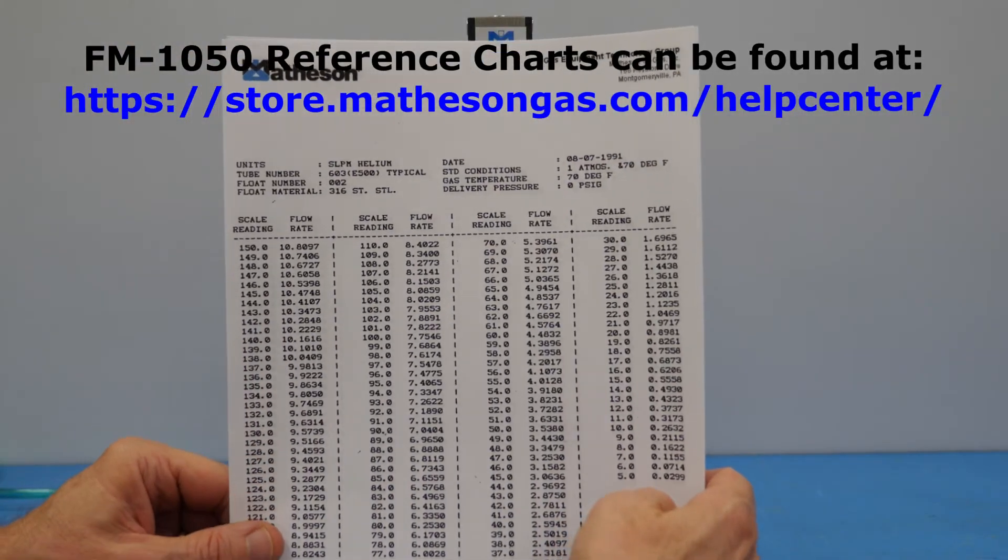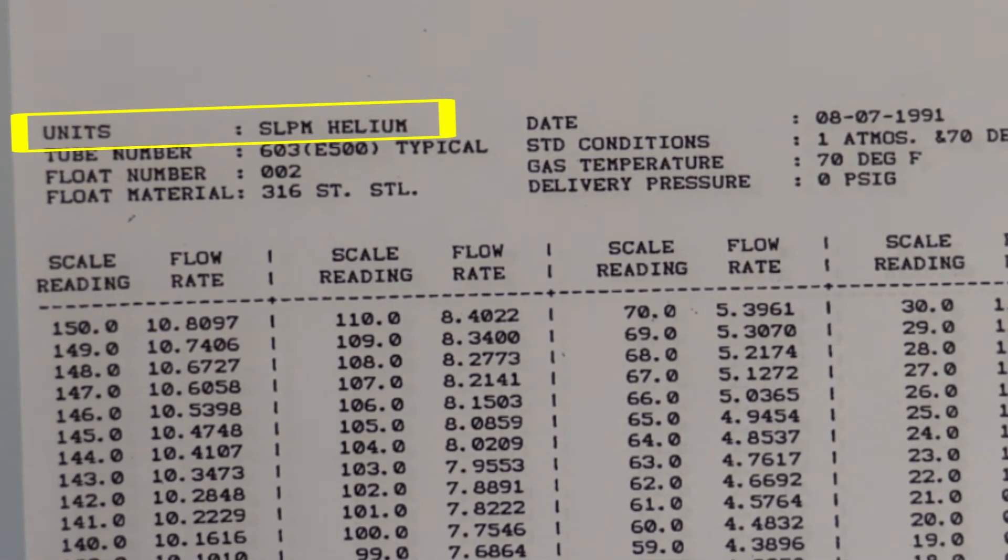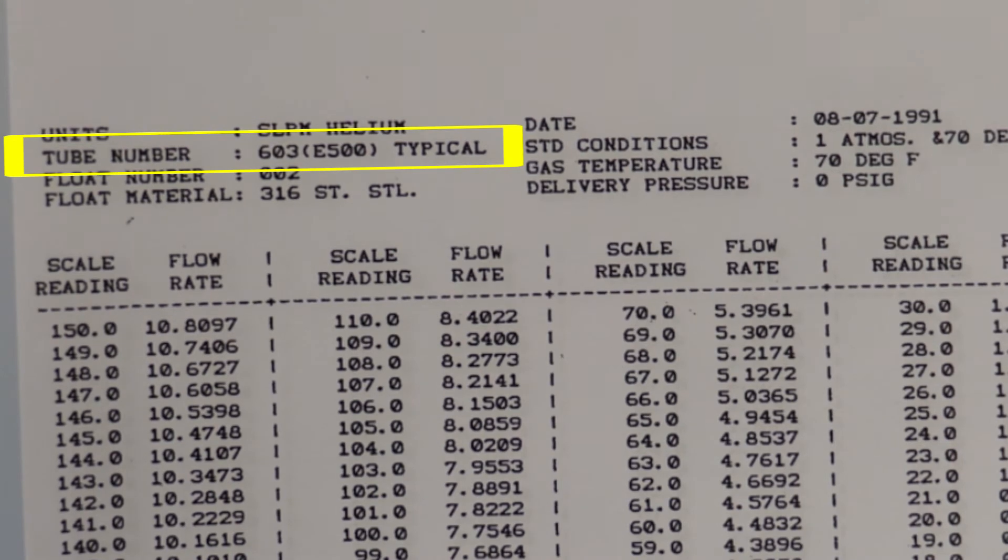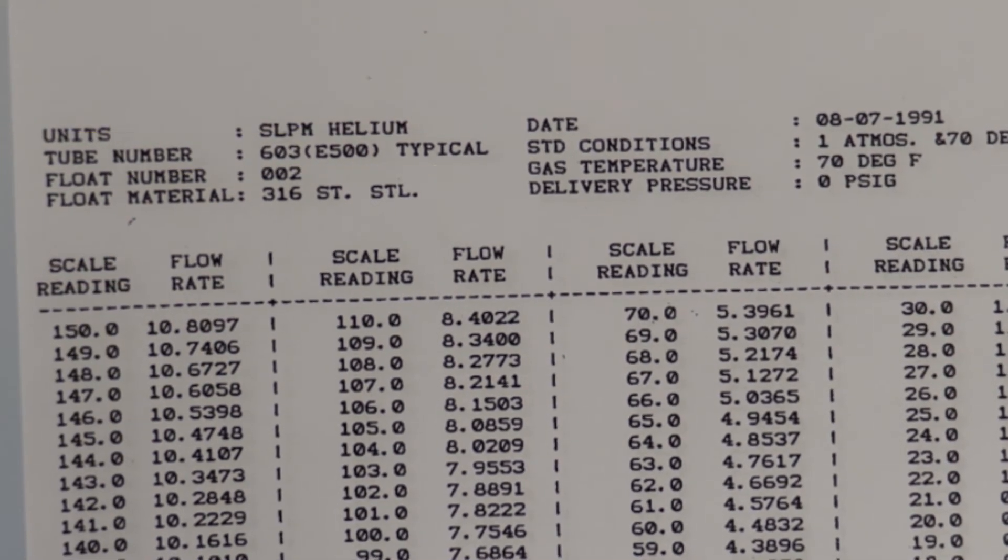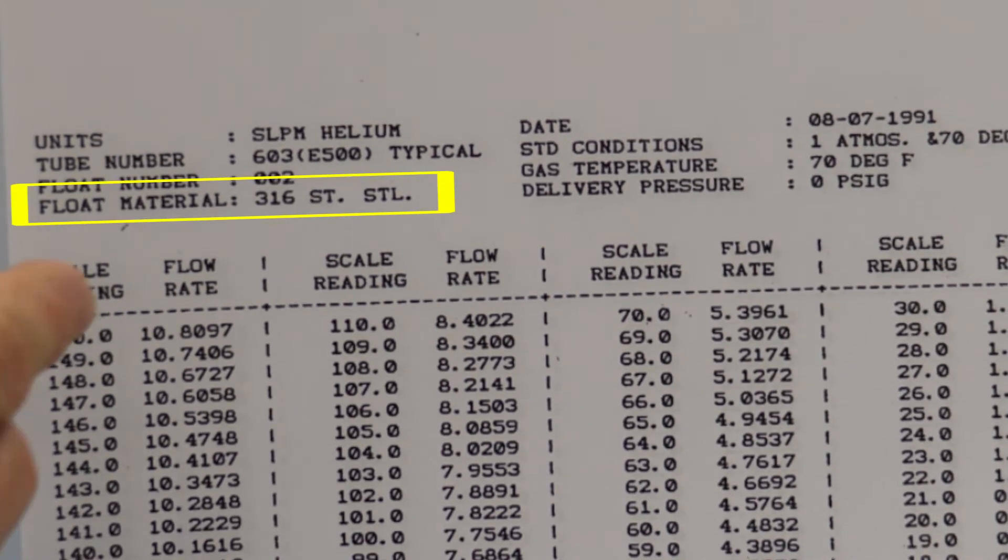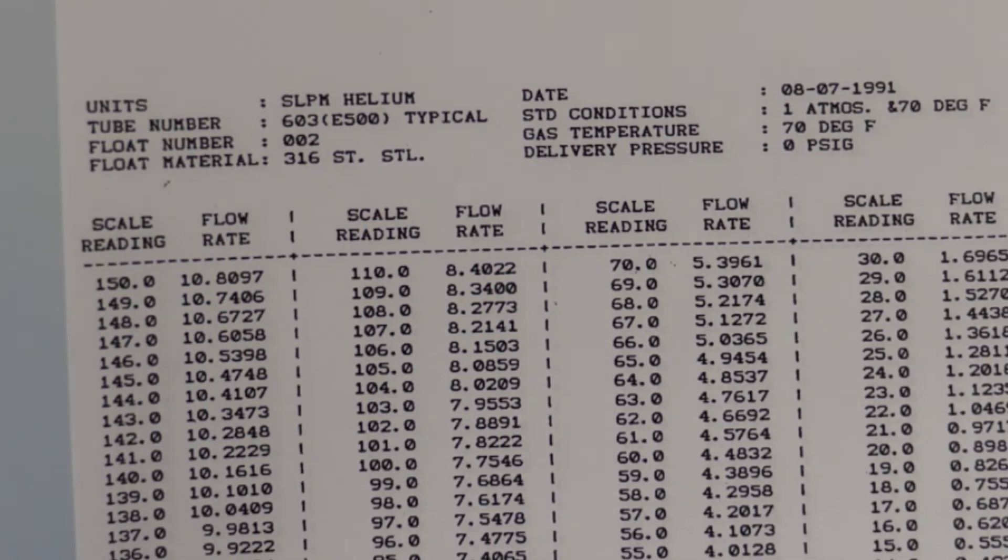Again we take a look at our flow curve. In this case, the units are standard liters per minute helium. The tube number is 603 E500, which is what we want. That's what we have in our meter. The float material is 316 stainless steel, and the delivery pressure being 0 psi G is what we want.